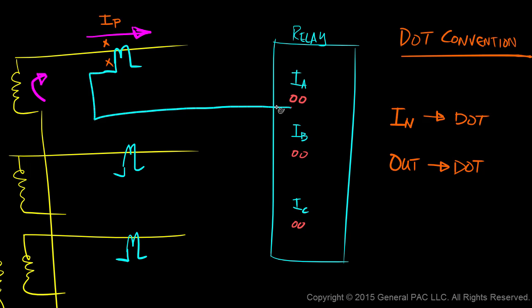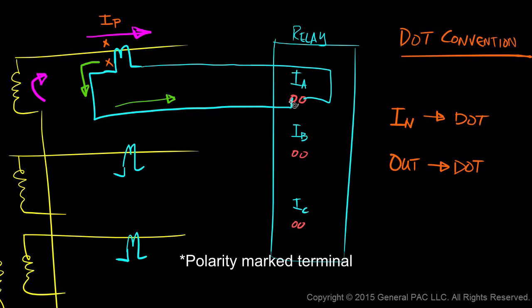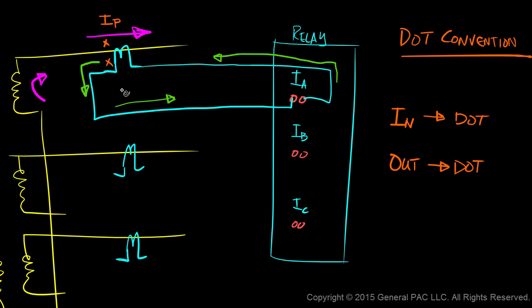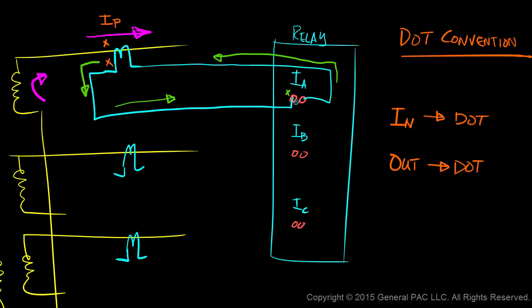Let's connect our CT this particular way. Primary current flows into the dot on the primary side, so secondary current must flow out of the dot on the secondary side. Secondary current flows through this polarity mark here, comes out of this polarity mark, and creates this circulating current. Because there's a dot on this side, we would expect that this contact on the relay is the polarity side of that contact. These two sides should match up.